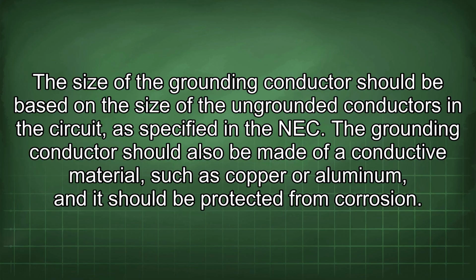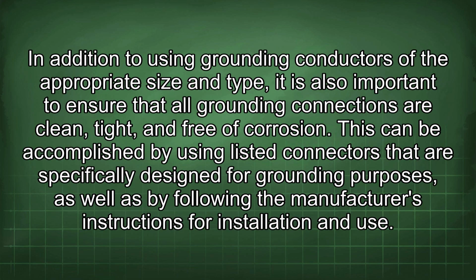The grounding conductor should also be made of a conductive material, such as copper or aluminum, and it should be protected from corrosion. In addition to using grounding conductors of the appropriate size and type, it is also important to ensure that all grounding connections are clean, tight, and free of corrosion. This can be accomplished by using listed connectors that are specifically designed for grounding purposes, as well as by following the manufacturer's instructions for installation and use.